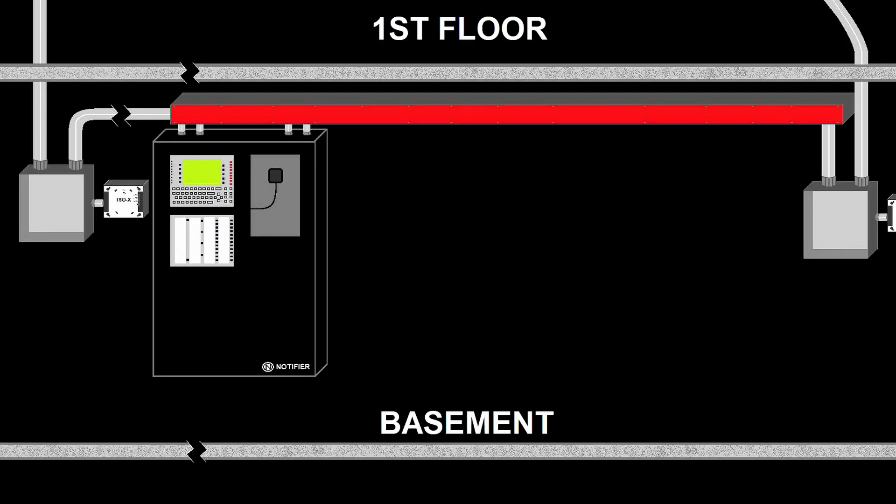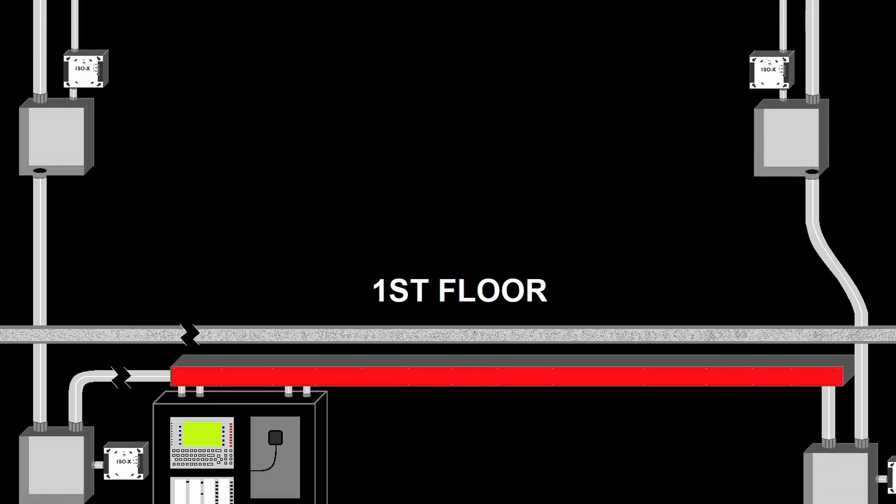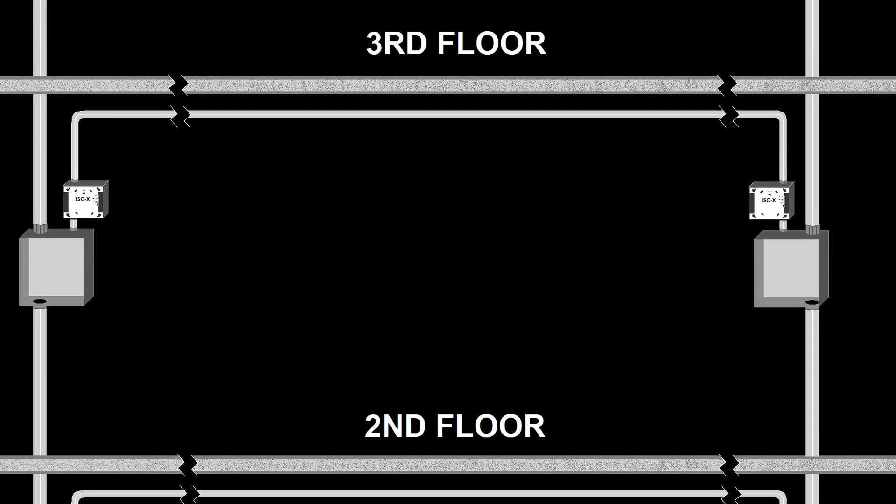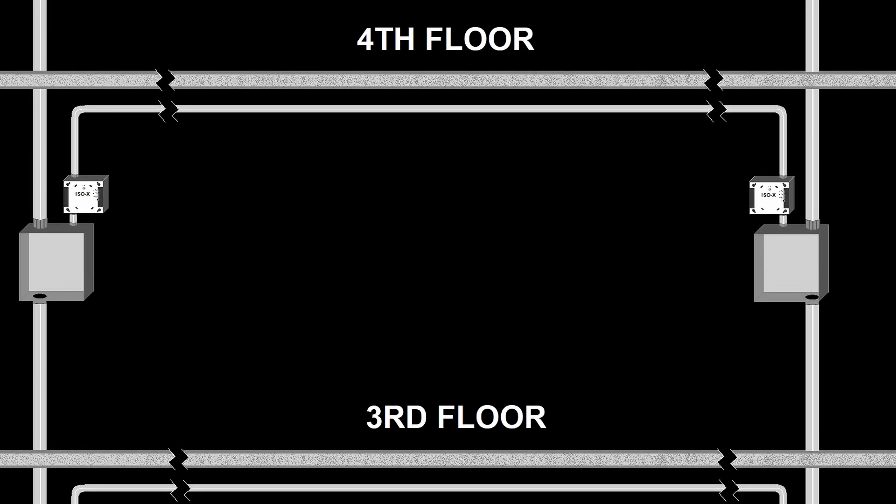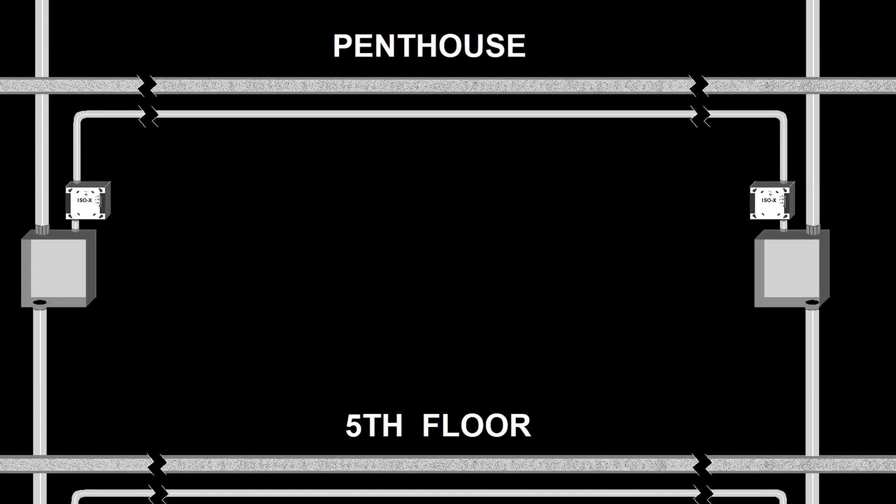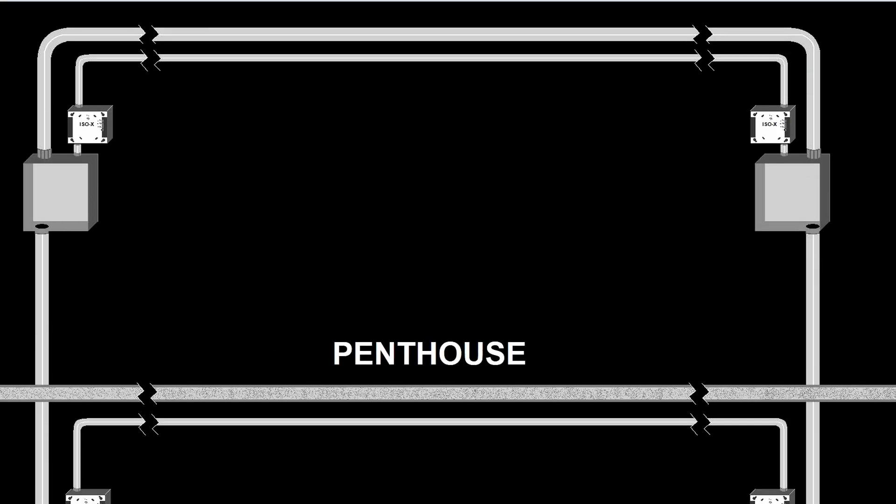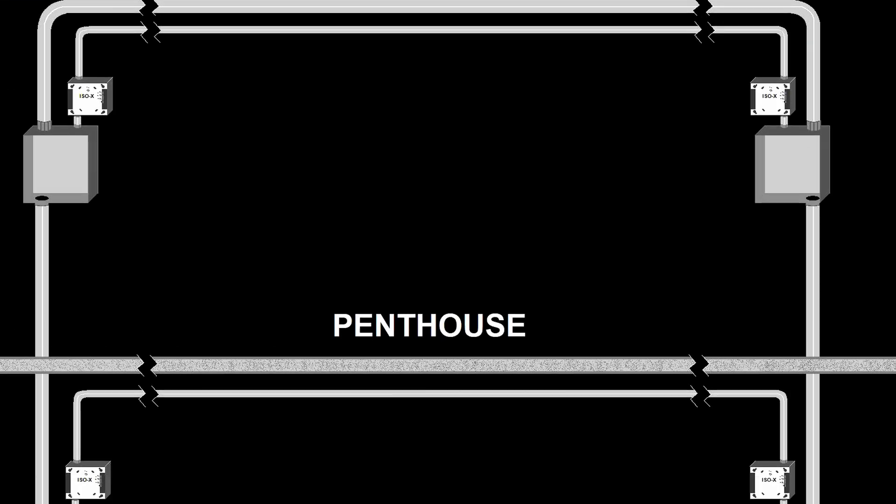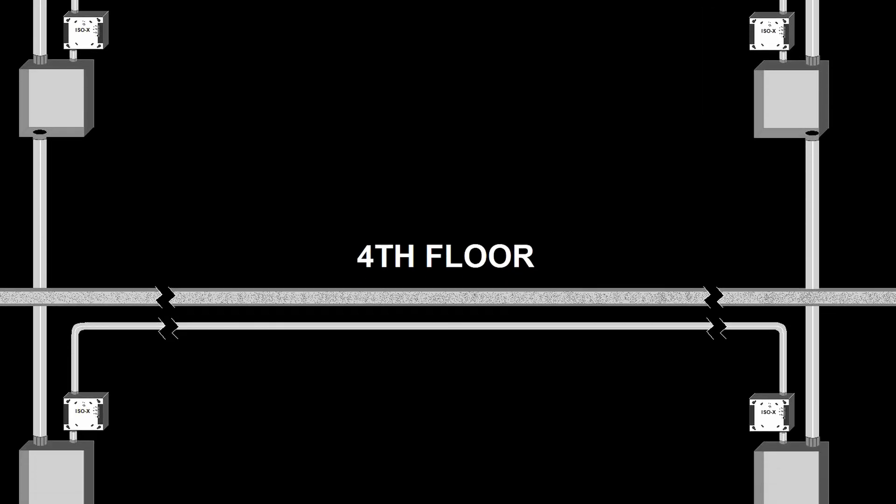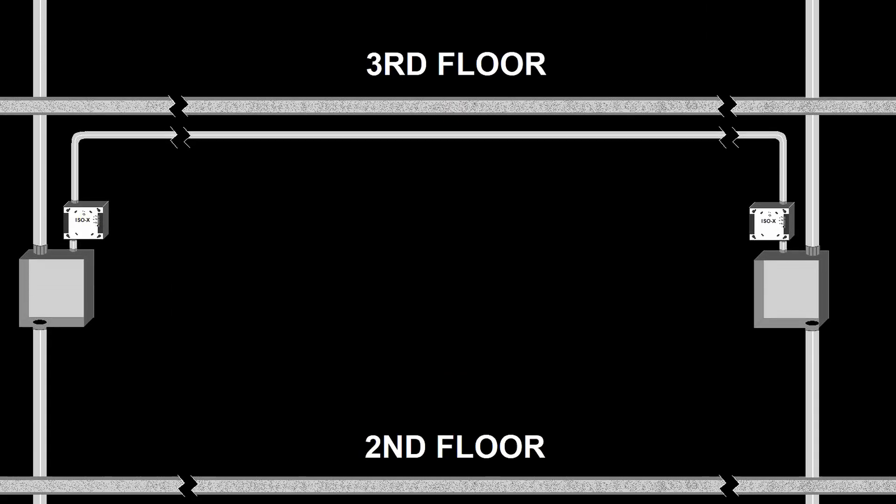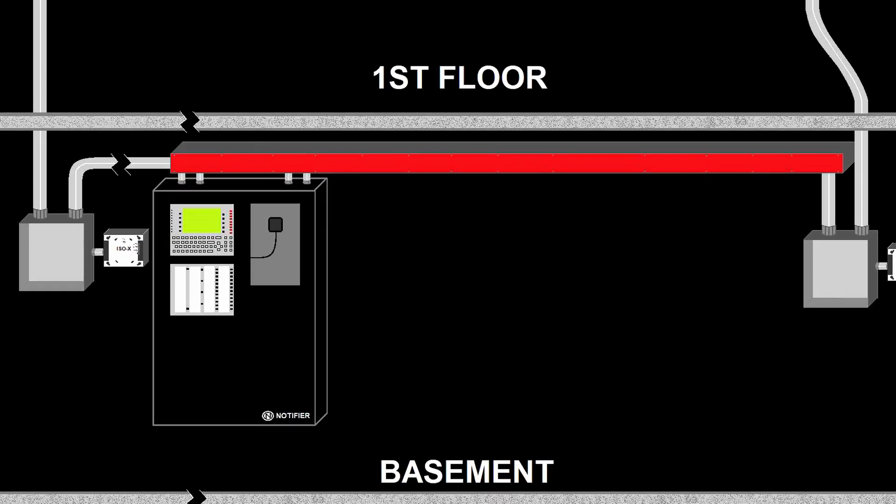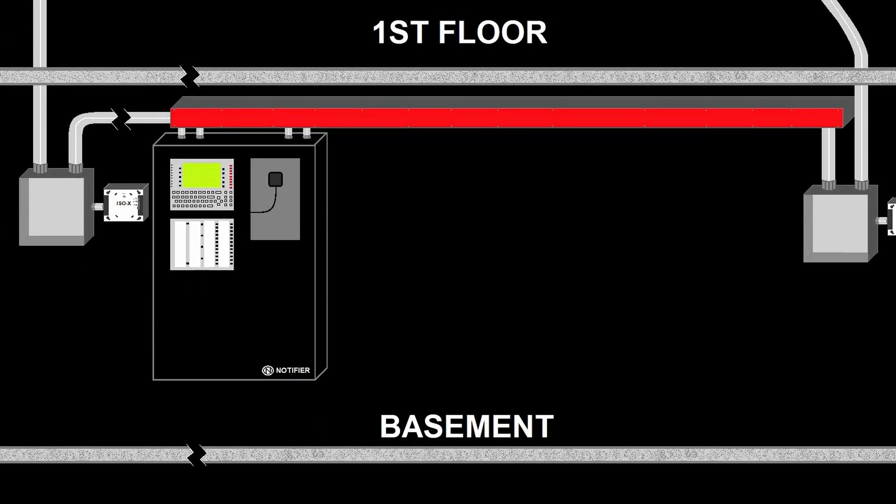The SLC loops will travel up the building through the fire alarm riser closet. When a loop reaches the floor it's covering, it will leave the Hoffman box and enter an isolator module. After the isolator module, it will go into the first device on the circuit and then out of that into the next one and so on until it reaches every device. Then it will go into another isolator module before returning back to the panel through a separate riser closet. As you go to each floor, there will be one less SLC circuit in the Hoffman box than the floor below it had until the penthouse just has one SLC loop.